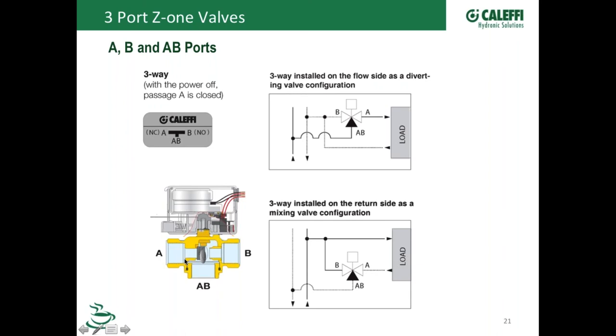And then when you power the normally closed actuator, it'll reverse that to where A will be open and B will be closed. We get quite a few calls, not quite a few, but every now and then, where a guy will have one of these things and it's piped backwards. And so when it's not powered, it's going to the wrong direction. And we do offer, like we mentioned before, our normally open actuators.